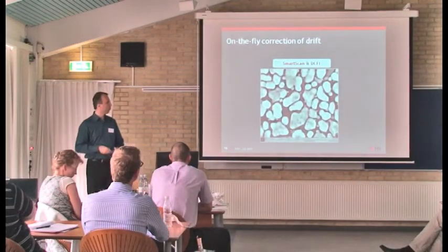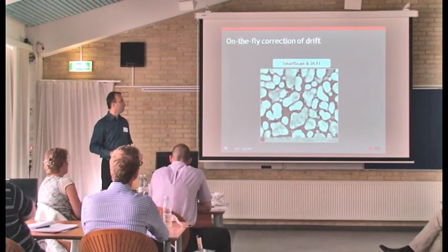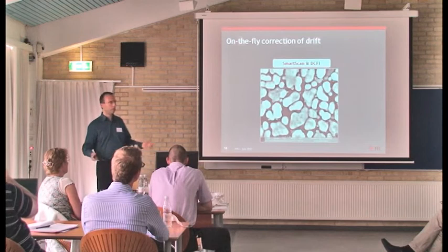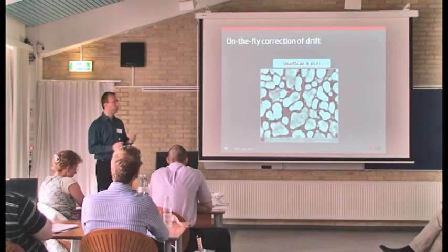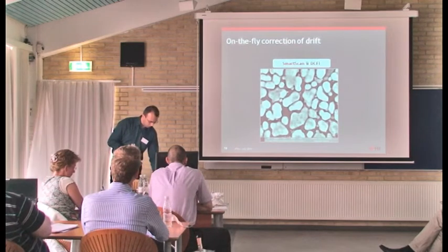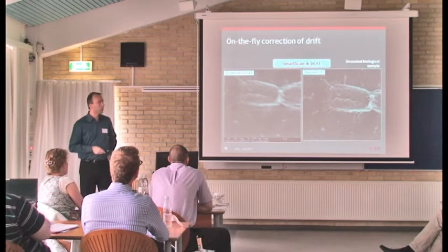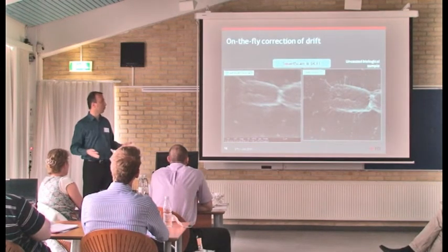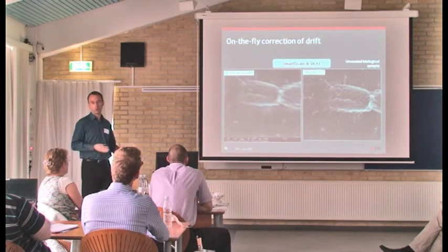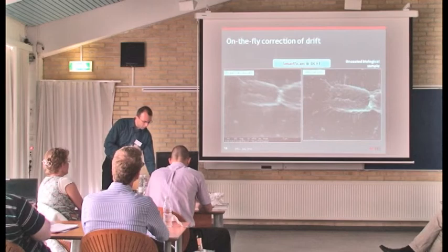Then correction of drift. Just to explain very quickly what is available here, it's really built into the DualBeam, and it allows on-the-fly correction for drift by means of image realignment. Practically, what this means is that with traditional scanning, if I'm experiencing drift, for instance related to charging or the stage, I can get back to completely stable images.